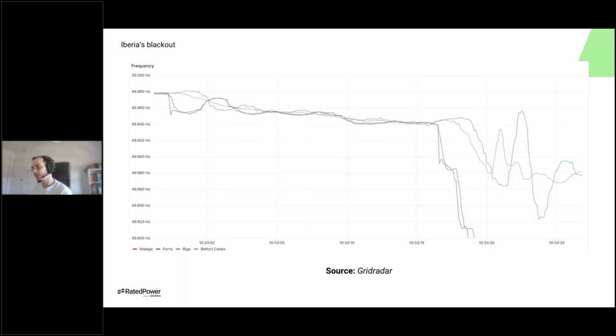So again, this is obtained from Grid Radar. This represents the frequency during the blackout. And the first thing that we can observe is that at 12:32 and 57 seconds, we had this drop in frequency, and this was produced by a generator loss, something that can happen, and the network was perfectly prepared for this. We see that the frequency dropped, but then immediately frequency containment reserves jumped into place, and the frequency was contained at around 49.95 hertz. However, this frequency, instead of going back to normal, went down a bit, but it still was within reasonable levels where other generators shouldn't have failed.